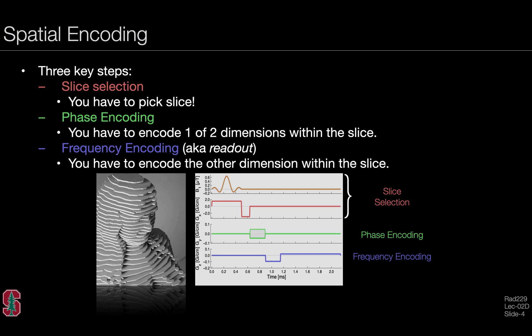Spatial encoding includes three key steps. Slice selection, that is, you have to pick a slice. Phase encoding, in that you have to encode one of two dimensions within the slice. And frequency encoding, also known as readout, you have to encode the other dimension within the slice. And these events happen in sequence: you first slice select, then phase encode, and then frequency encode for conventional Cartesian k-space imaging.